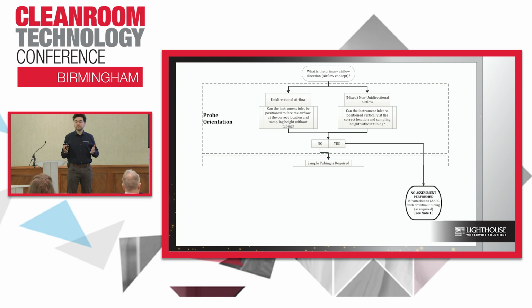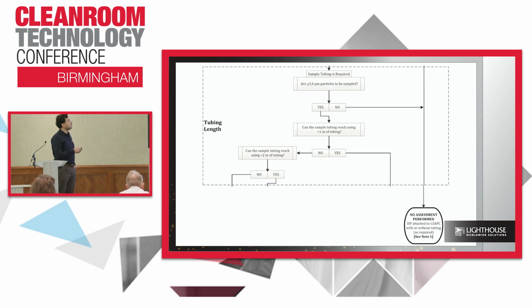You can continue. If you connect your isokinetic probe directly to your particle counter, no additional risk assessment is necessary. But if you say, okay, I have to have a unidirectional flow, but I'm not able to put my isokinetic probe directly together with my particle counter, then sample tubing is required. So the idea here is that we have the probe orientation as number one, and the second is the tubing length. So can you do it within a certain distance? If not, then you continue this way.